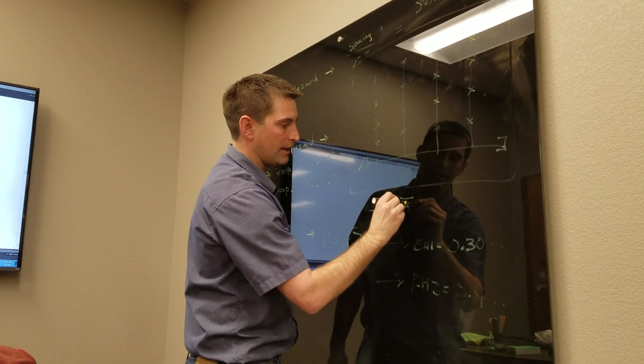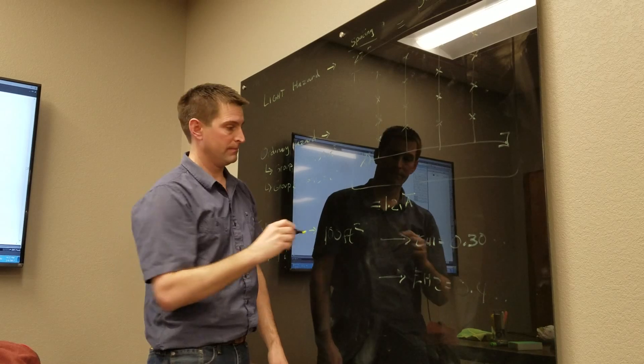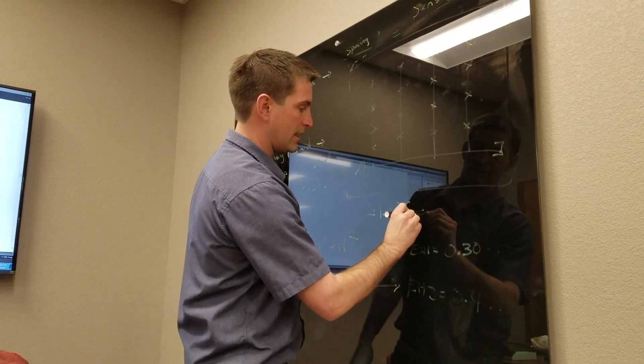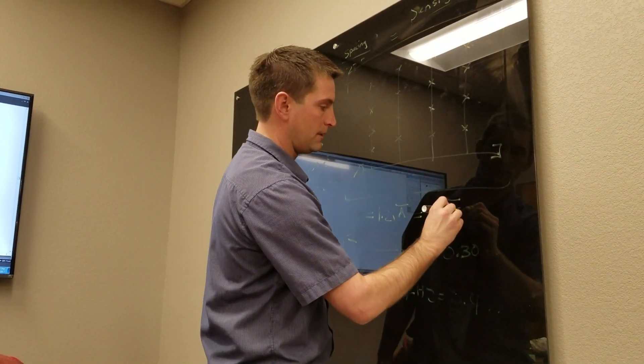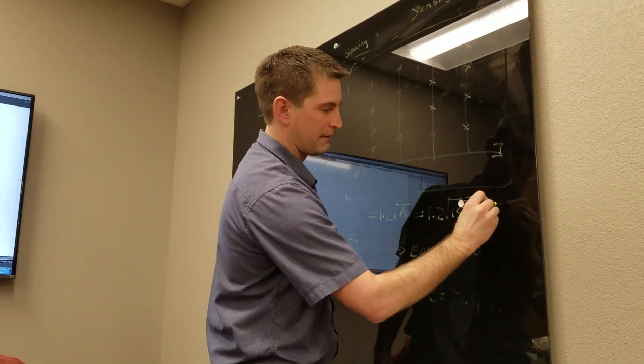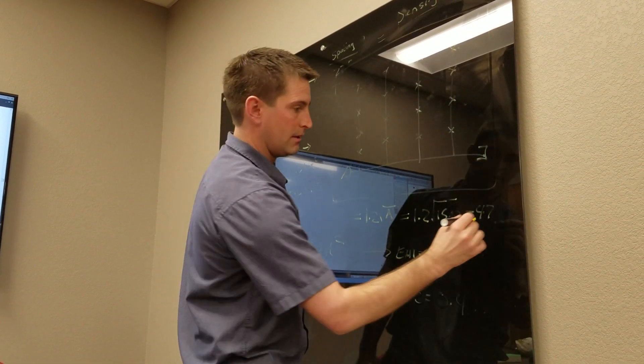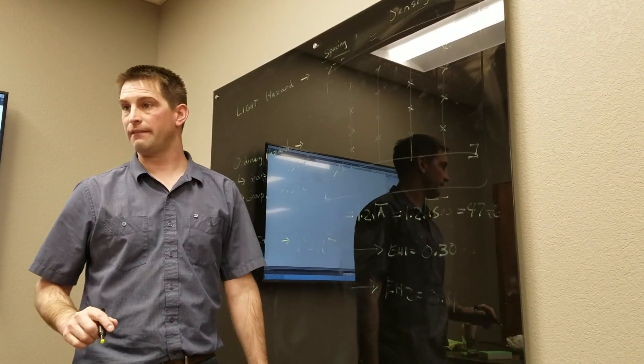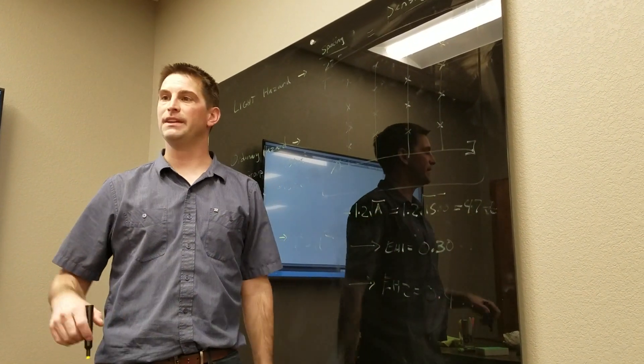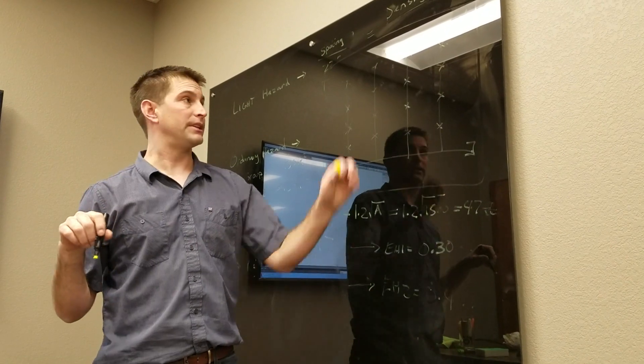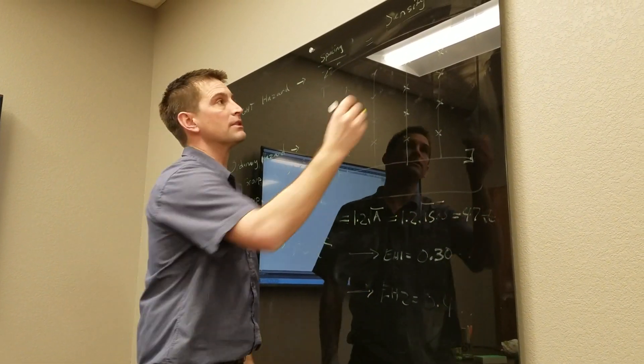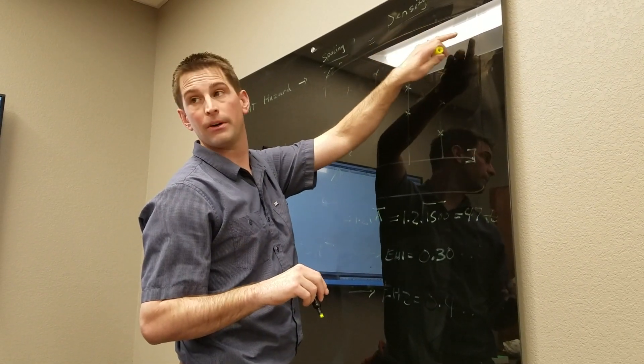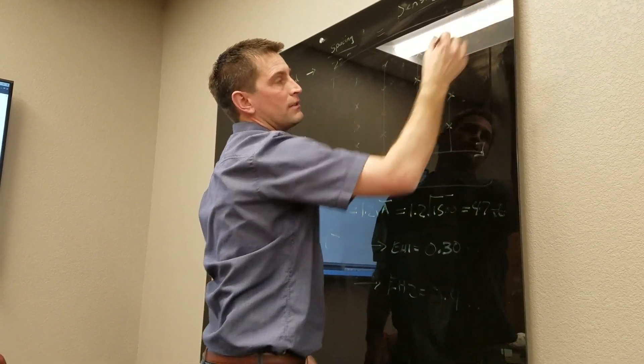What is our area? 1,500. So I would say 1.2 times the square root of 1,500. It's roughly 47 feet. So 1.2 times the square root of 1,500 is about 47. So I have to go 47 feet on the long length of my rectangle parallel to my branch line. So I say where's the furthest point? This head is the farthest one. It protects to this wall and to that wall, so its protection is all the way to that corner. Start there.